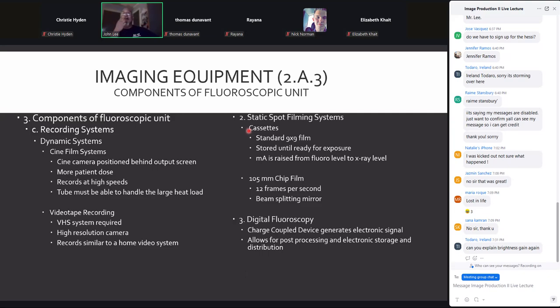This is why there was like a 2 to 3 second delay, 1 to 2 seconds maybe on a fast system, because the film physically had to be moved into position in order for the images to be recorded. They would use 9x9s or in some instances 14x14 cassettes that held film in them. The disadvantage here, again, is the MA has to be raised to X-ray level as opposed to fluoro level, which is at about 2 to 3, maybe 5 MA. Now we have to go to hundreds of MA, so that takes a little time, again, to get that thermionic emission to occur and give us enough electrons.